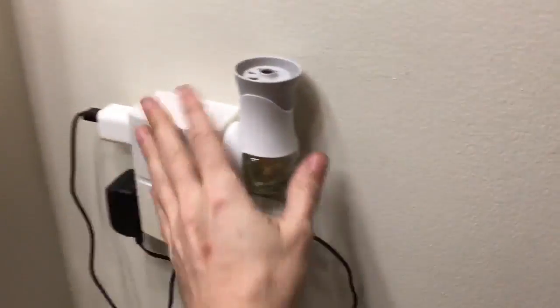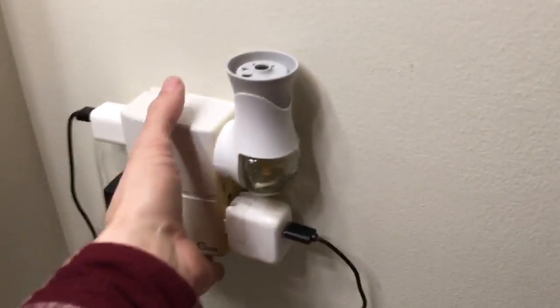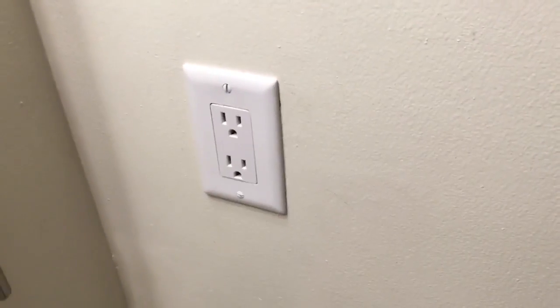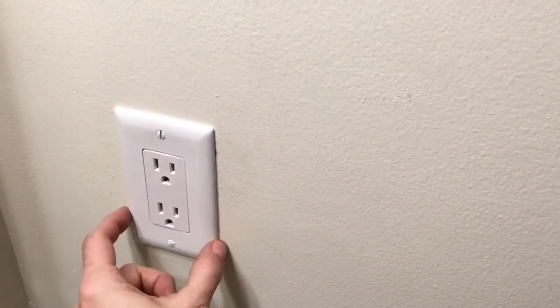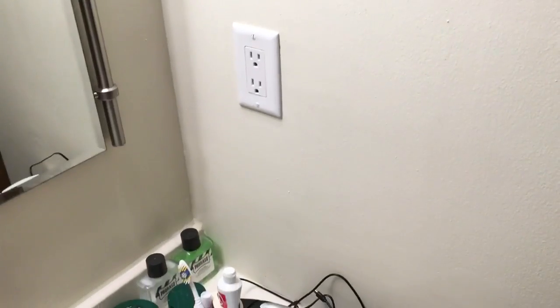But this particular outlet set up here, and this is cold, sorry, I know the answer, is actually this outlet ties. You notice this isn't a GFI of its own, which you would expect to see in a bathroom to have its own GFI. What they did is they actually put a single GFI on one bathroom on one circuit. It's all within the same 20 amp breaker that actually ties the upstairs outlet next to the sink in the bathroom to the master bathroom, which I would expect to be on a GFI. It also ties my garage, and it ties that downstairs bathroom together. So now we have a couple of different variable possibilities to figure out what is going on here.